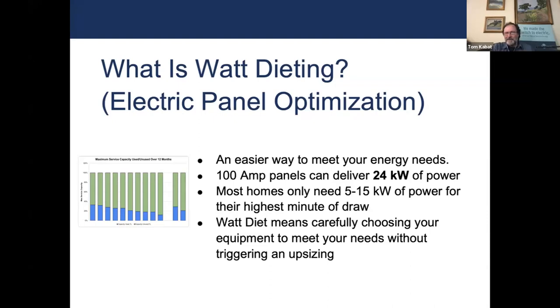That little graphic to the left shows the results of measuring a dozen homes, how much of their electric panel they were using and how much they had unused. The blue part at the bottom was their peak electric usage for the whole year, the highest 15 minutes of any quarter hour in the whole year. The top of the green bar is the amount of electrical panel capacity they had. So that's just a small sample - we've now seen data sets with thousands of homes sampled, and it's pretty much the same result.